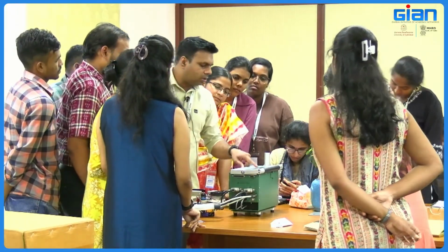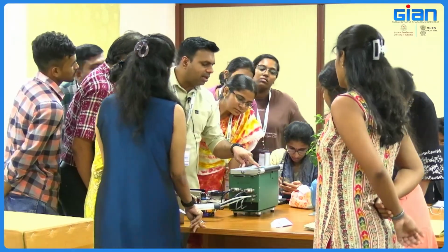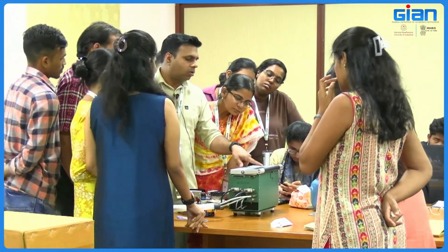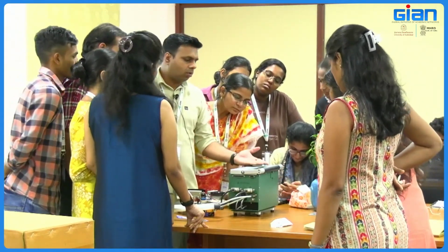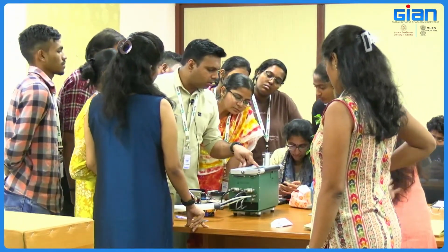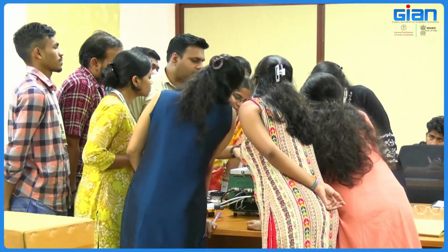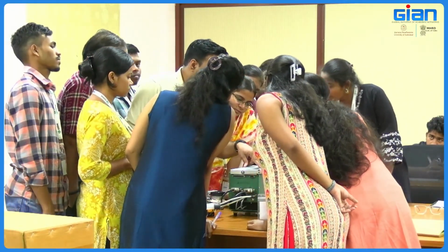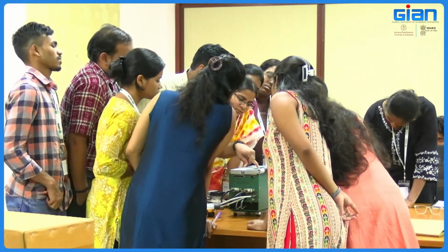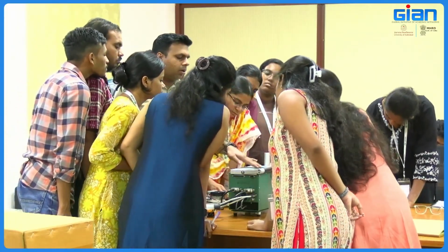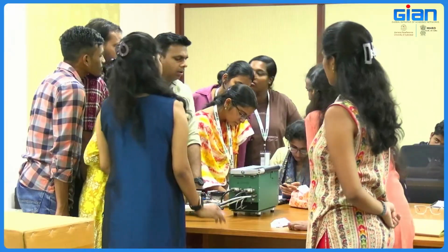Okay. So you can just go to CO2 reference, sample 0. CO2 RS means R for reference, S for sample. So these two things you want to make 0. Got it? So you can just go here. It's not changing much, you see, 9.2 to minus 5.6. You just press F1, the one beneath this button. So setting 0 low, setting 0 high, then it will make the two values almost similar.